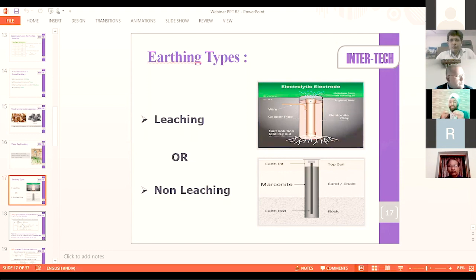But in the case of Marconite, you mix cement with the Marconite, and it becomes concrete. You can refer to the slab over your head - you can see that slab remaining there for generations, with the reinforcement remaining the same. So this concrete actually protects the conductor from corrosion, and this protection from corrosion gives you longevity and performance, because if no decay is happening, the performance will remain there forever.